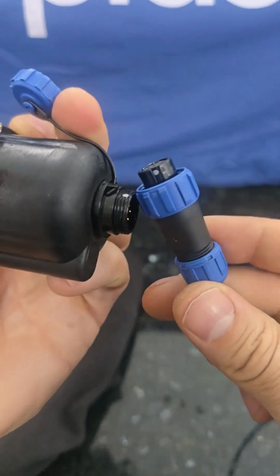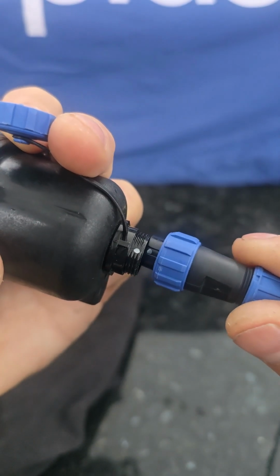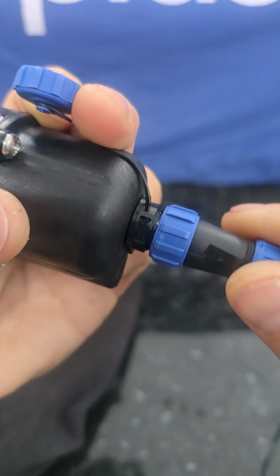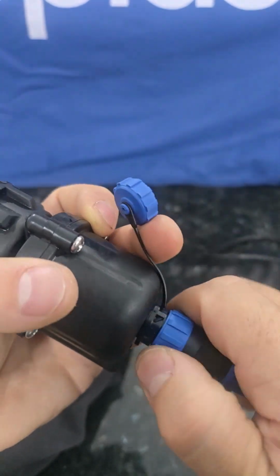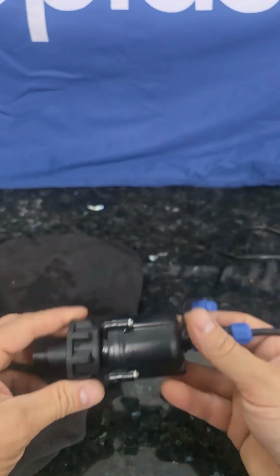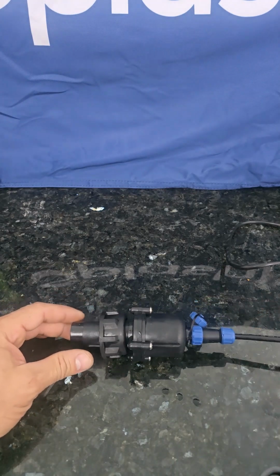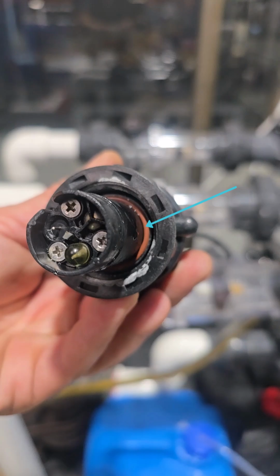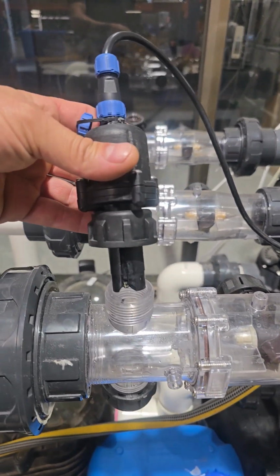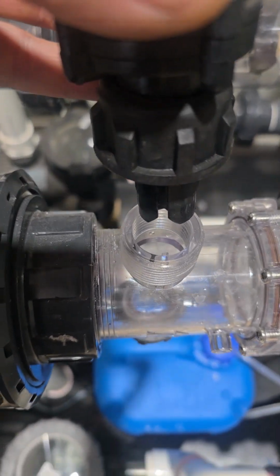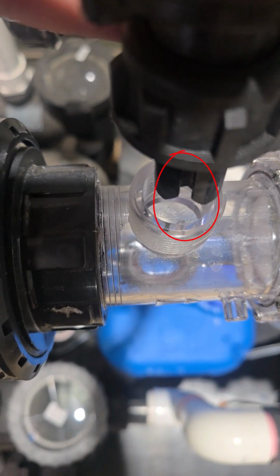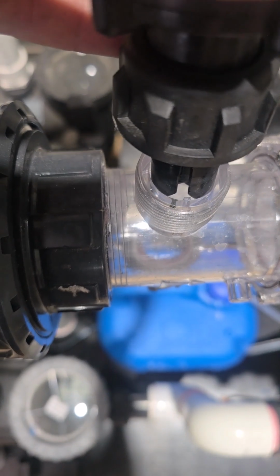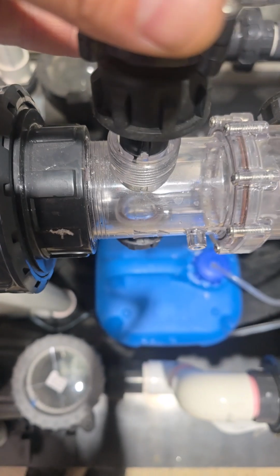To attach the cable to the multi-probe, make sure that the two white dots align. Once aligned, push in the plug, then gently tighten the blue nut. Before we refit the multi-probe, ensure the O-ring inside the probe is in position and clean from any debris. Then line up the keyway on the multi-probe to match the keyway in the flow sensor housing. Insert the multi-probe and hand tighten the nut in a clockwise direction.